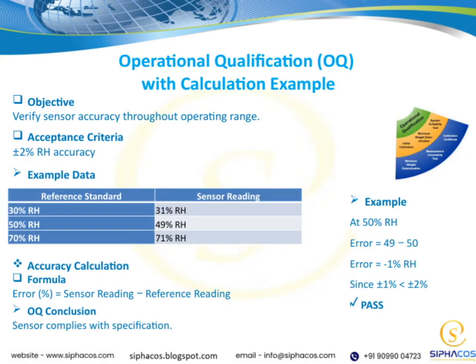Let's walk through an example of how we check sensor accuracy during operational qualification. Here, the sensor reads 49% relative humidity, while the reference standard says 50%. The error is just -1%, well within our acceptance range of plus or minus 2%. This means the sensor passes. We repeat this across the full range, confirming the sensor meets the accuracy criteria we set. It's a straightforward calculation, but essential for reliable performance.